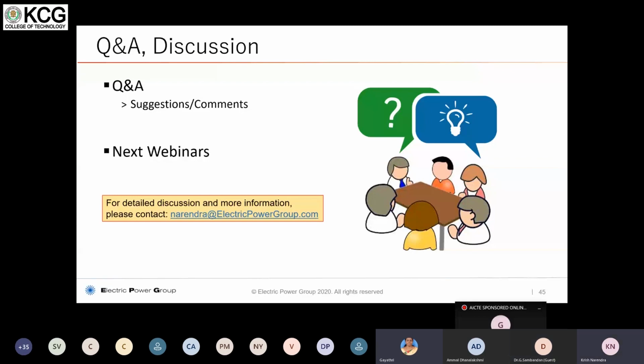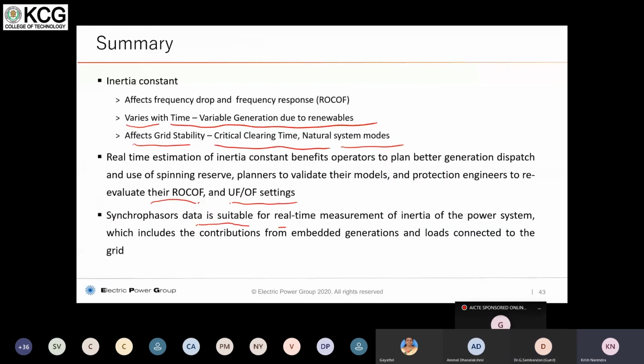That's exactly what I'm talking about. The biggest challenge would be, if 80% renewables are there in your system, and only 20% synchronous generation, then there are concepts such as virtual inertial support that can be applied to the grid, because now you have a lot of controllable devices, power controllable devices such as the inverter based controllers, so that they can provide and modulate the active power, so that, as I said in the equation, and if you go back to the equation, let me tell you how that is achieved.